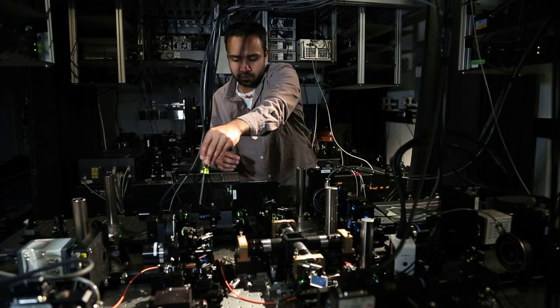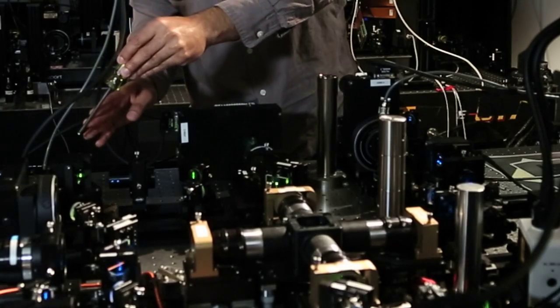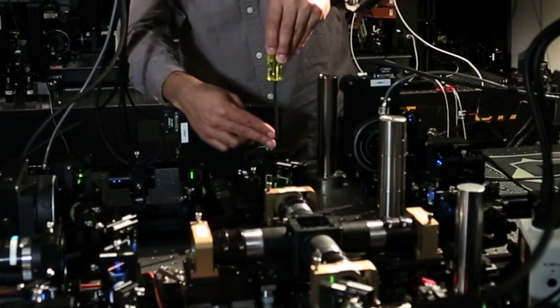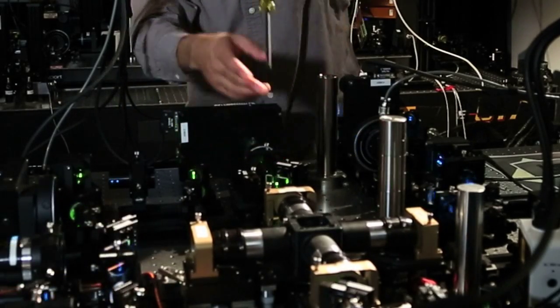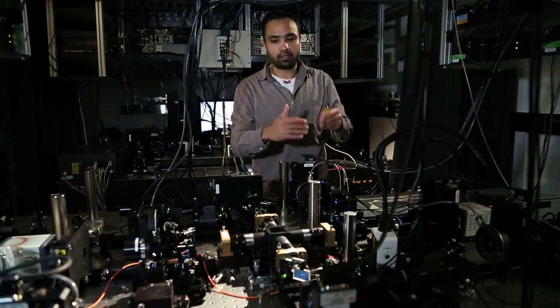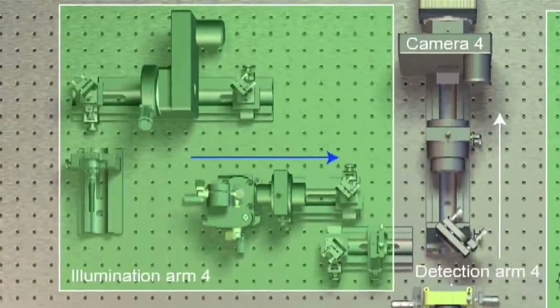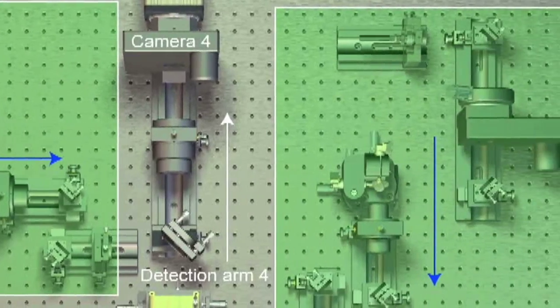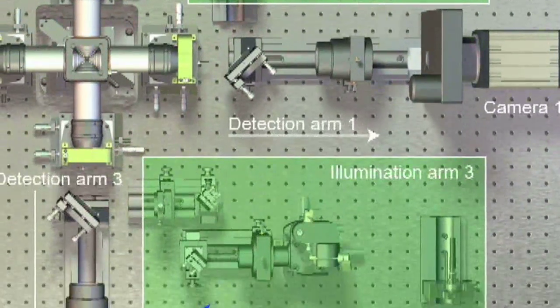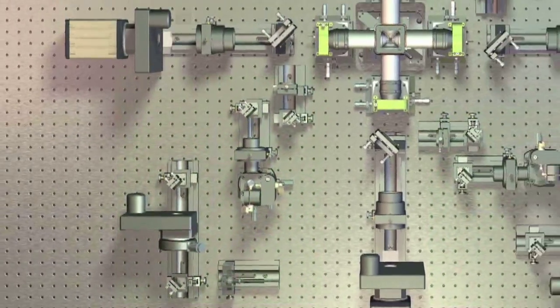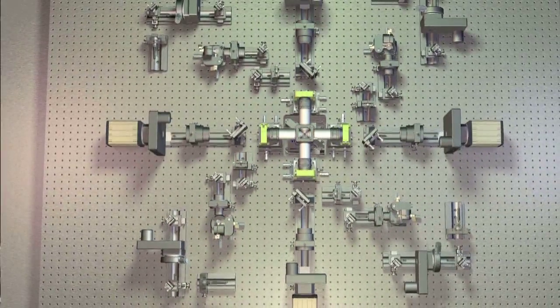Whereas illumination is past the XY galvo scanner, scan lens, illumination tube lens, dichroic mirror, objective onto the chamber. This basic setup is repeated four times in four different arms, and that allows us to generate light sheets from four different angles. The cameras at four different angles allow us to collect the fluorescence from four different angles, giving us isotropic resolution in our images.